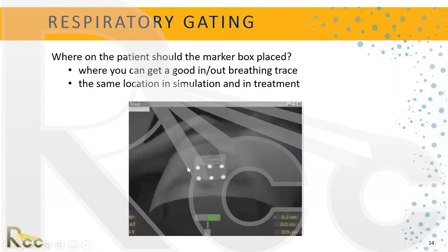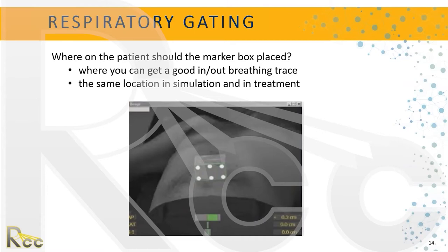Where should the marker box be placed? Here it's on the patient's abdomen. It's a small, lightweight plastic box with six reflector dots on one side — you have to place it so those dots are facing the camera, otherwise you won't get a good read and won't be able to trace the respiratory phases. It must be placed reproducibly every day, not hanging off to the side or placed randomly, and it must be in the same position every single day so the camera can see it and get a good breathing trace.